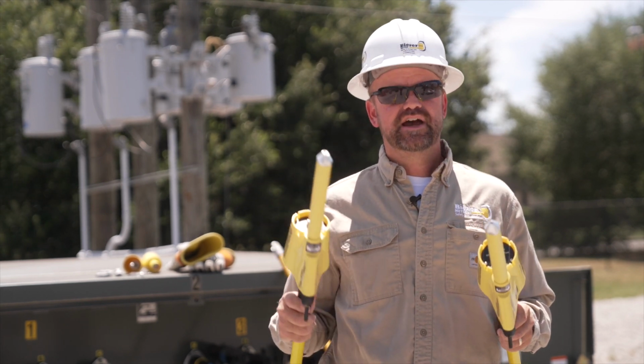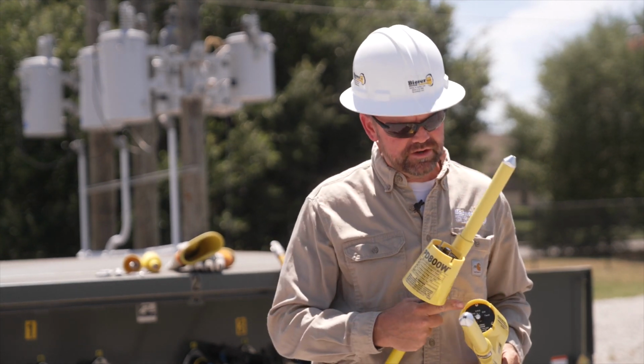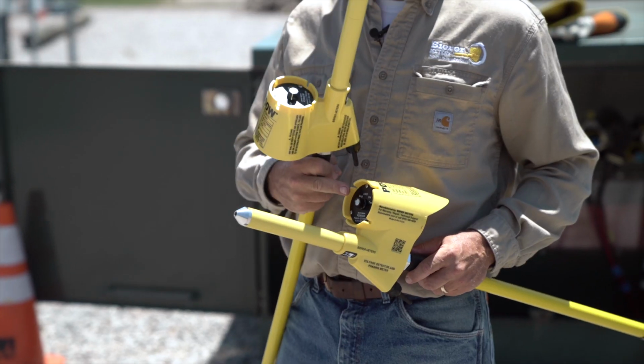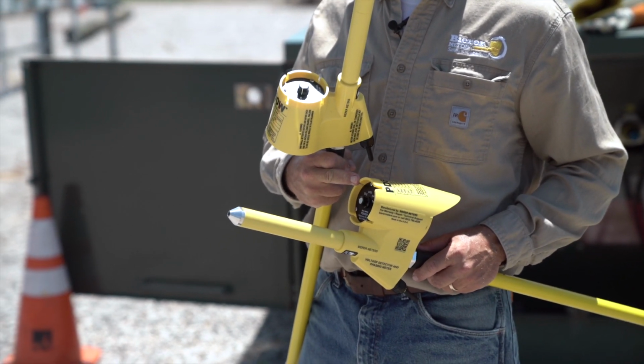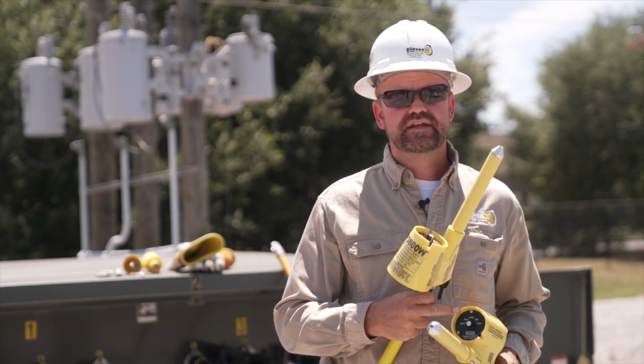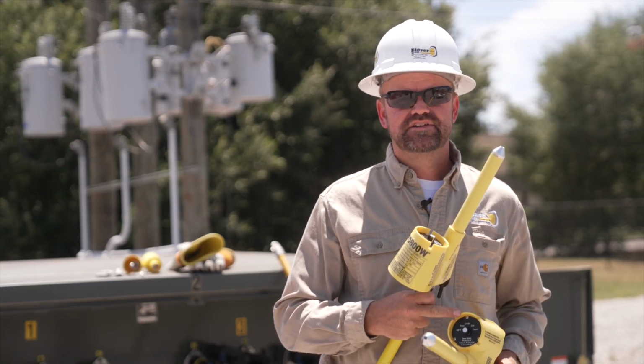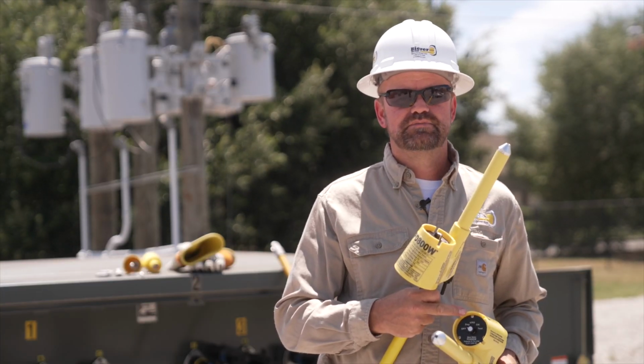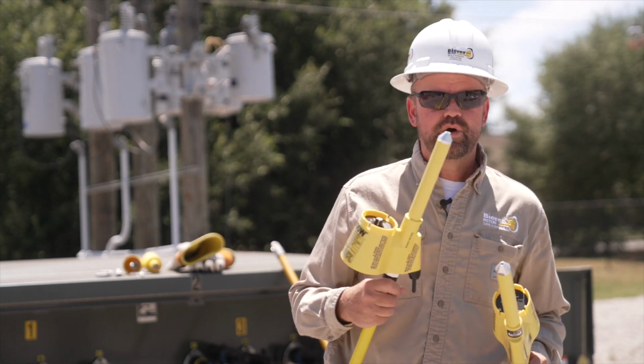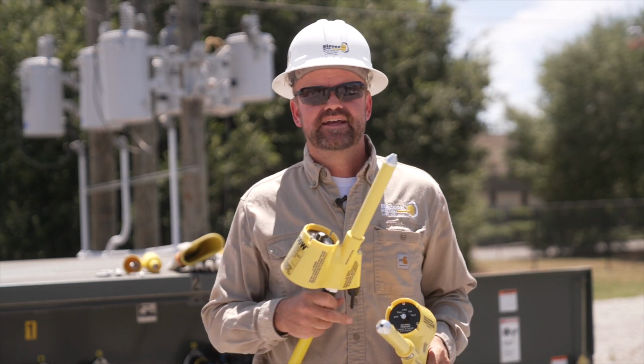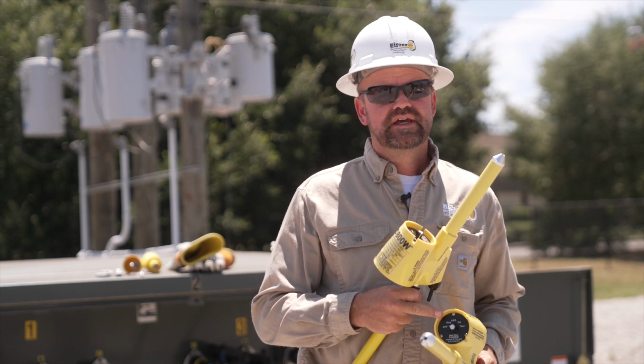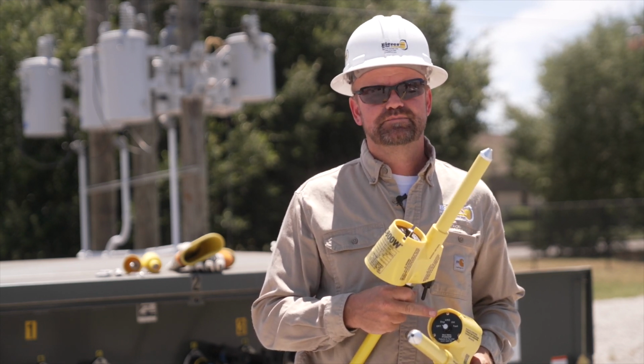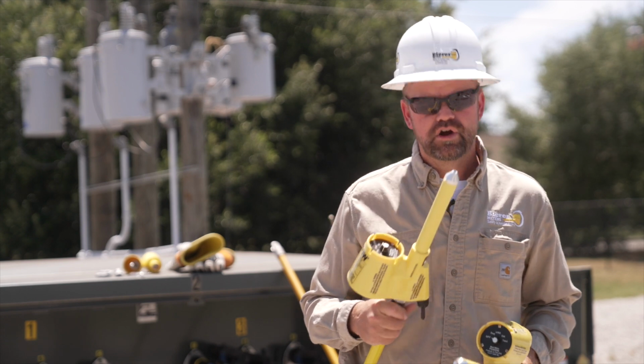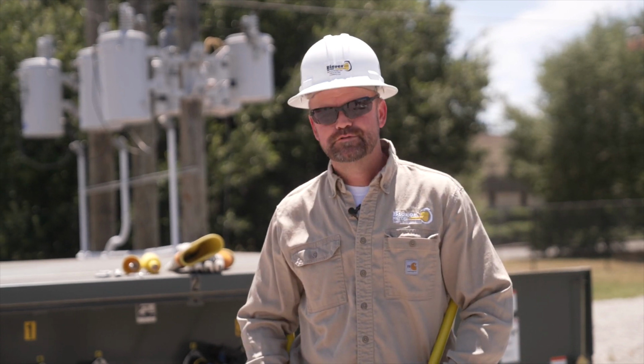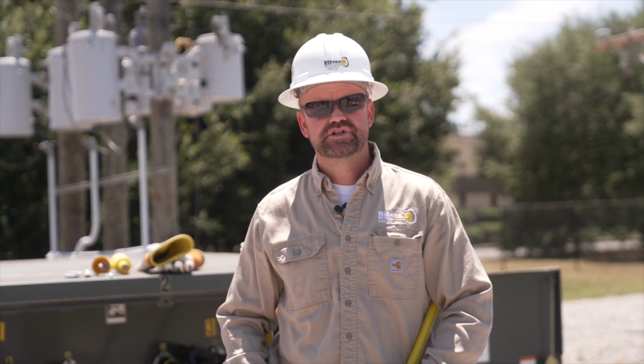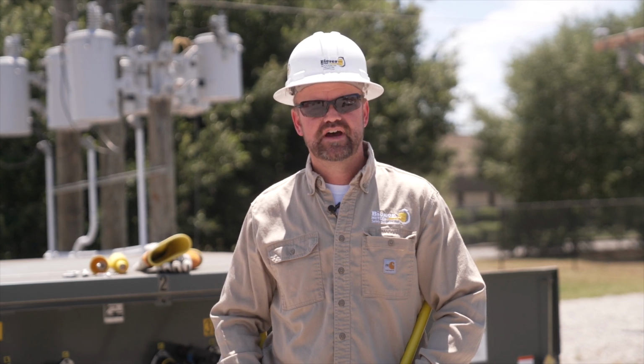So using the PD800W, you'll notice on the back of the device, the first position is off, the second position is DEG, which stands for degree. The third is URD, which stands again for underground residential distribution. The fourth is OH, which stands for overhead. And the fifth is a test position. You can self-test the devices prior to use, and also in a known voltage. So we have a dual phase power supply here below me, which is usually in the box in your kit when you get the device.